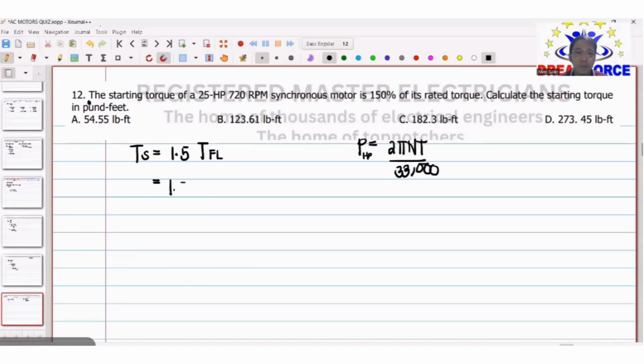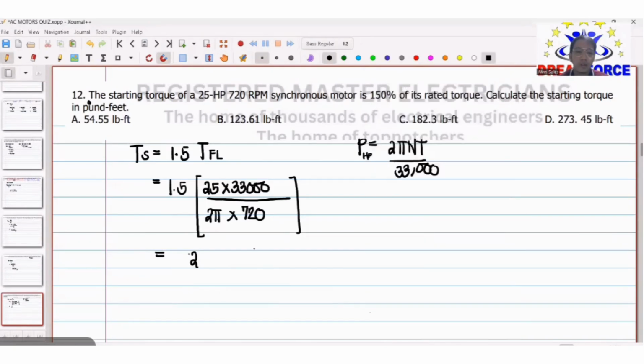So let's solve now for your full load torque. So that is 1.5 multiplied by the power in HP, that is 25 HP, times 33,000 divided by 2 pi times your N. So the N is 720. This is your NR. Okay, so it is simply 1.5 times 25 times 33,000 over 2 pi times 720. So 273.45 pound-feet. Okay, that is letter D. Next number 13.